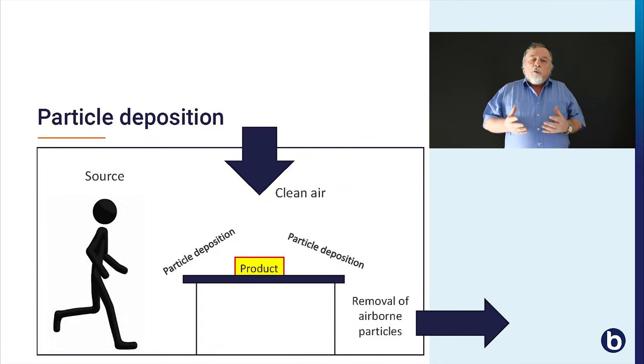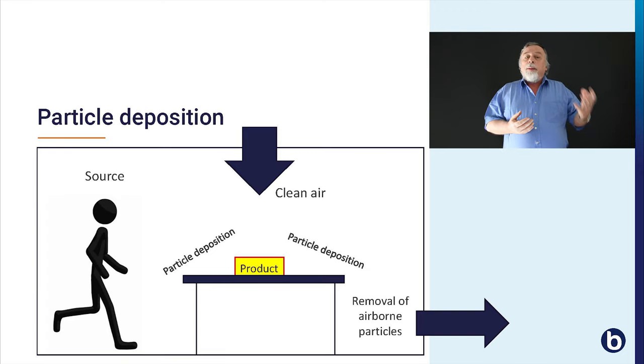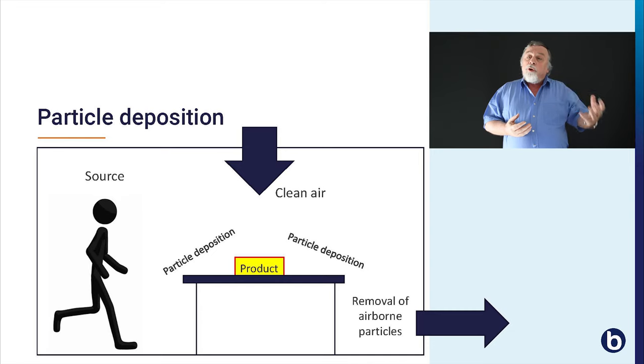Here you see a diagram with a product on a table and a person. In a clean room, people are the major source of contamination — a person sheds skin particles and microorganisms. The air around this person is mixed with clean filtered air so that the resulting concentration of particles in the air reduces. The airflow removes all airborne particles out of the clean room, but large particles that cannot stay in this air flow will deposit on all surfaces.